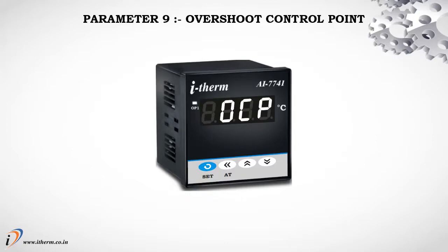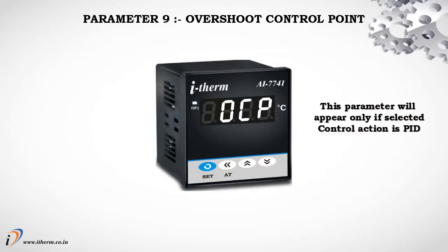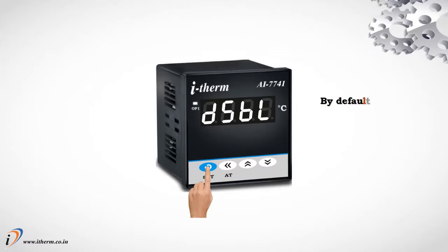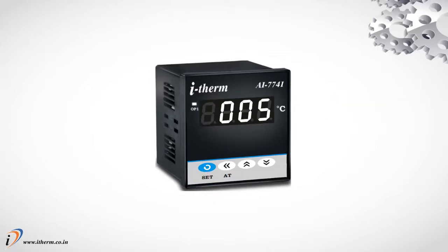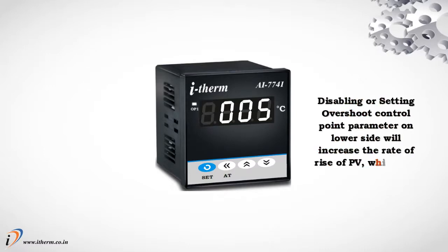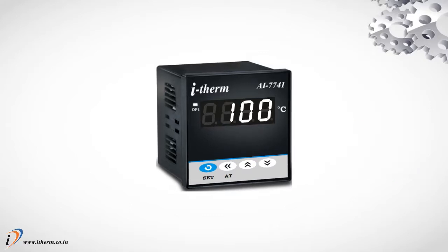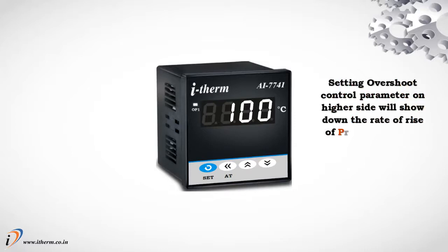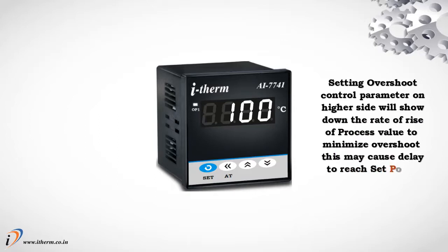Parameter 9. Overshoot control point. This parameter will appear only if selected control action is PID. By default, value of overshoot control point is disable. Disabling or setting overshoot control point parameter on lower side will increase the rate of rise of process value, which may cause overshoot. Setting overshoot control parameter on higher side will slow down the rate of rise of process value to minimize overshoot. This may cause delay to reach set point.